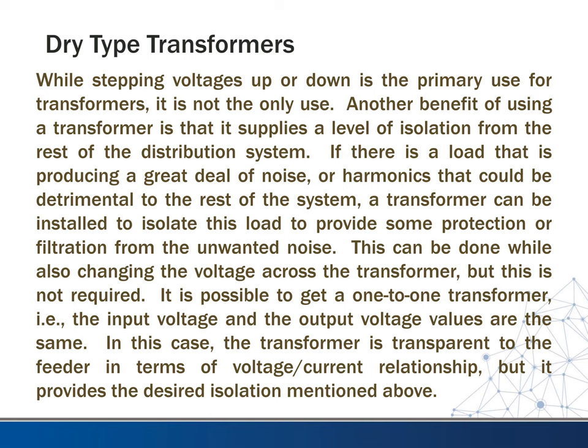Some motors can be noisy, but also if you have a lot of digital equipment somewhere in a location, that digital equipment's going to produce a lot of harmonics as things are switching and they're using square wave signals or anything like that. So that can put a lot of noise back on our power line. So sometimes we might want to put an isolation transformer in there to help filter some of that out.